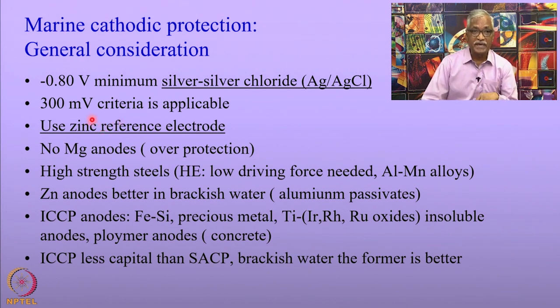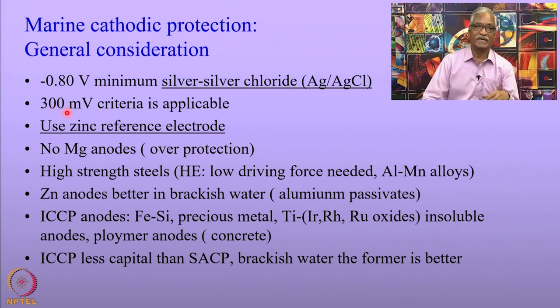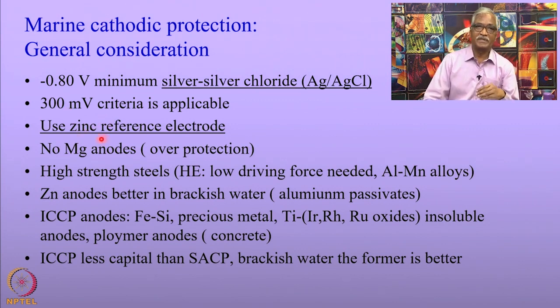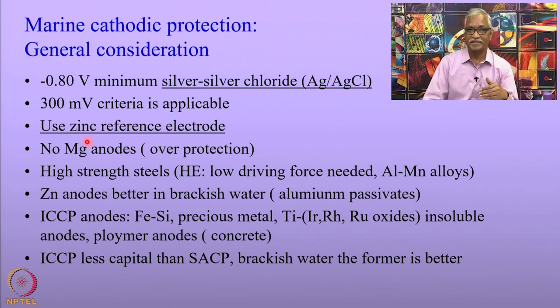You can also use the 300 millivolt shift criterion, because the electrolyte is highly conducting and the IR drop in the electrolyte is not very high. However, this does not take into consideration the resistance offered within the metallic structures. Use of zinc as a reference electrode is very common, because zinc is less polarized anodically and its potential does not change significantly when used as a reference electrode.